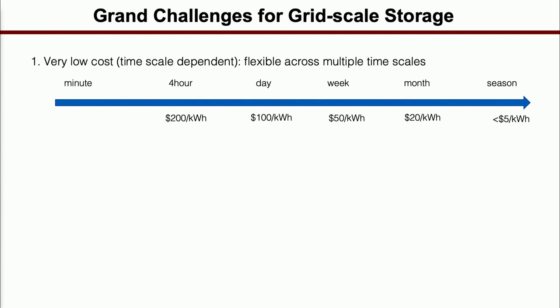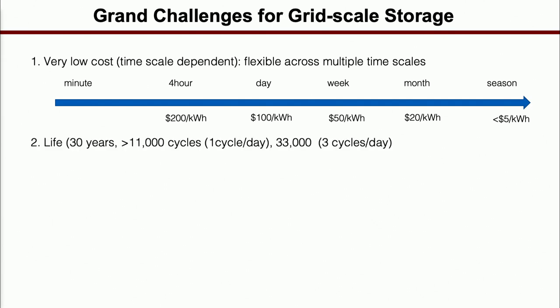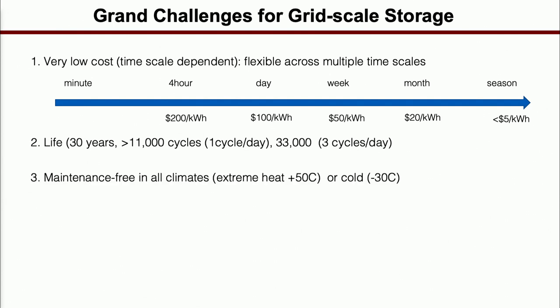Battery has the potential cost to go down to twenty dollars per kilowatt hour, but I haven't seen anything that could reasonably allow you to go below ten. The next consideration is lifetime. If you use one day per cycle, you need eleven thousand cycles; three cycles per day requires much more cycle life. And you need it to be maintenance-free at all climate conditions — very low and very high temperature. Currently lithium-ion requires air conditioning, but your solar is probably in a hot environment and wind in a cold one. You need safety and cradle-to-cradle recyclability.